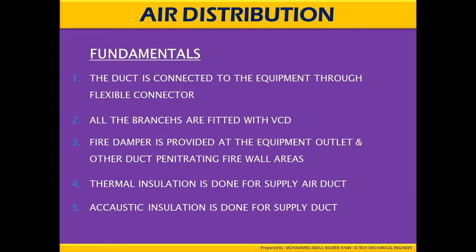A duct connects to the equipment through flexible connectors. All branches are fitted with a VCD — volume control damper. A fire damper is provided at the equipment outlet and at other ducts penetrating fire wall areas. Thermal insulation and acoustic insulation are both done for the supply air duct.